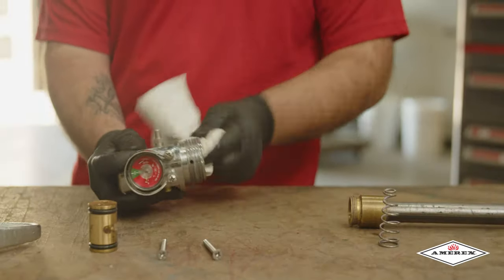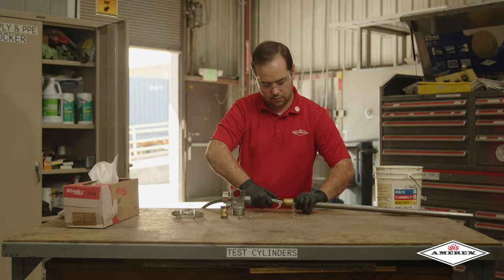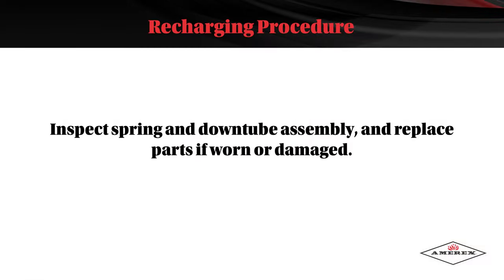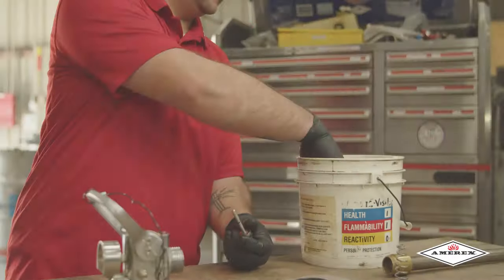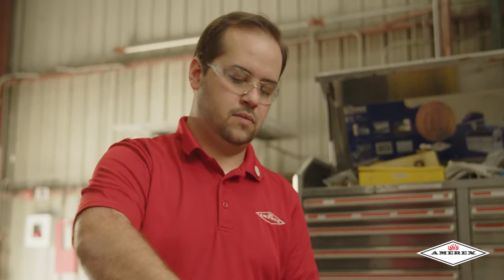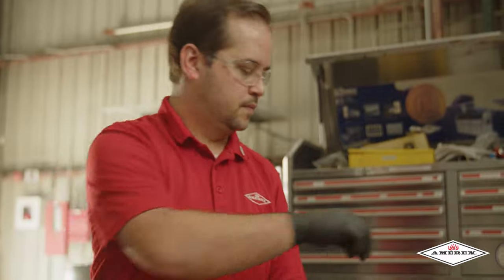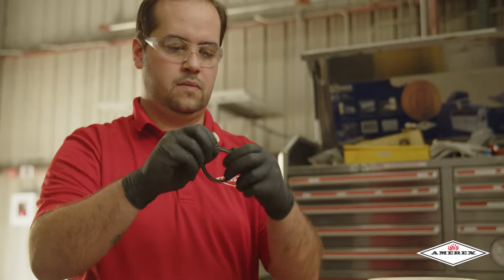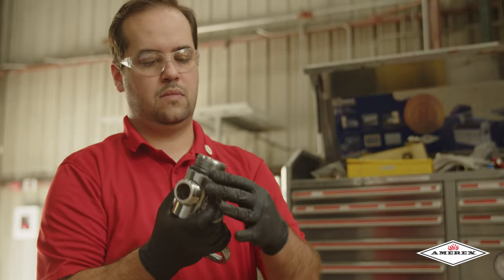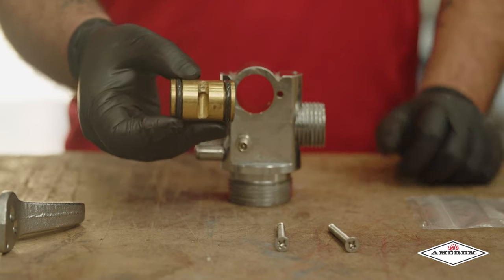Thoroughly clean all parts of the disassembled valve with a soft bristle brush or soft cloth. Blow the valve out with air or nitrogen. Inspect the spring and down tube assembly and replace parts if worn or damaged. Install a new valve stem and collar O-ring after lightly lubricating with an Amerex approved lubricant. Reassemble the valve assembly including the down tube, and set aside.